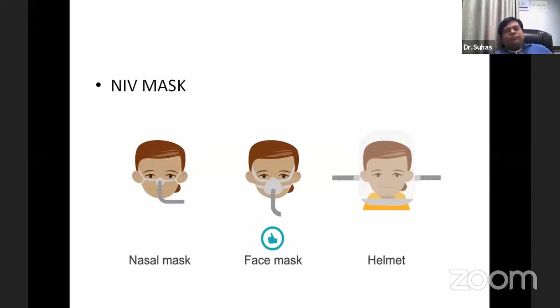Now, invasive ventilation. You all know it is very much like in an adult, but there are a few things we have to keep in mind when we are ventilating a pediatric patient. We have to switch on a pediatric mode. If we are on adult mode, the volume of delivery in the pressure or volume mode, whichever mode we set, will not be appropriate. So we have to switch to a pediatric mode, and if the patient is a neonate, you have to switch on the neonatal mode. Before putting a patient on invasive ventilation, we have to make sure the ventilator contains pediatric and neonatal modes or not.